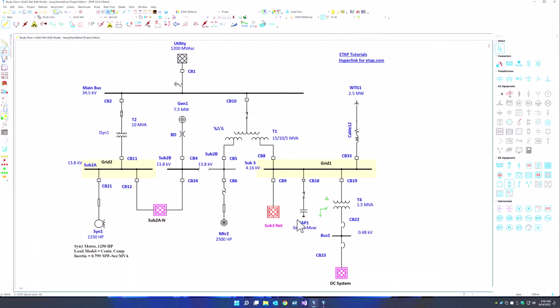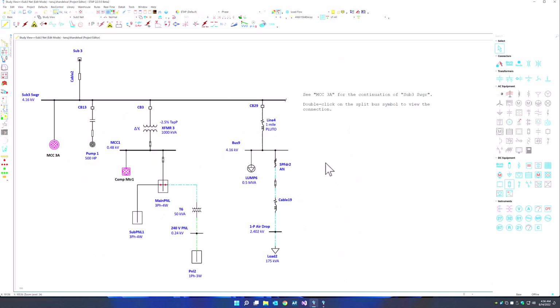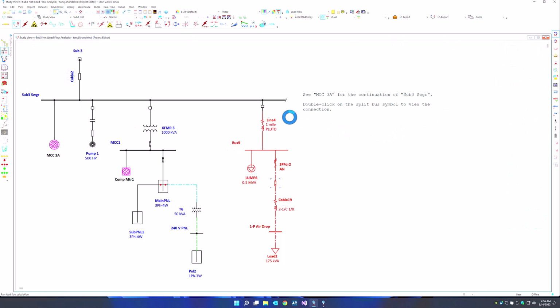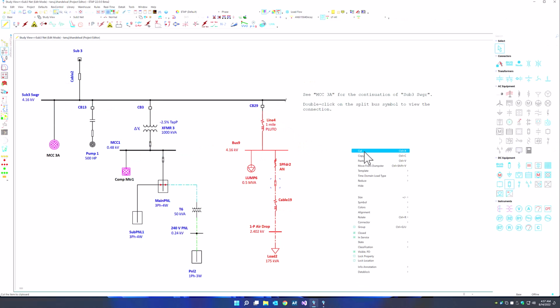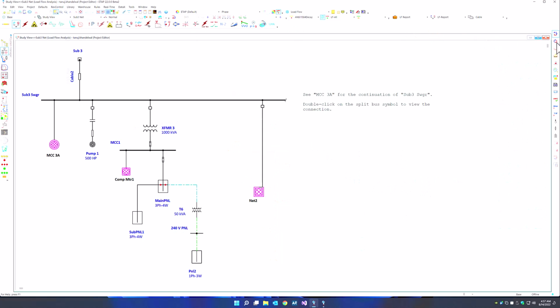We can simply find our main diagram and go inside a composite network, so we are one layer deep within the diagram. We can select a portion of the system. Before we do that, let's run a power flow calculation so we can see what the flow results are. And we have 85.9 amps. We can simply right click, tell the program to convert this to a composite network, and we can go back and run our power flow once more, and we can see it's exactly the same flow again.